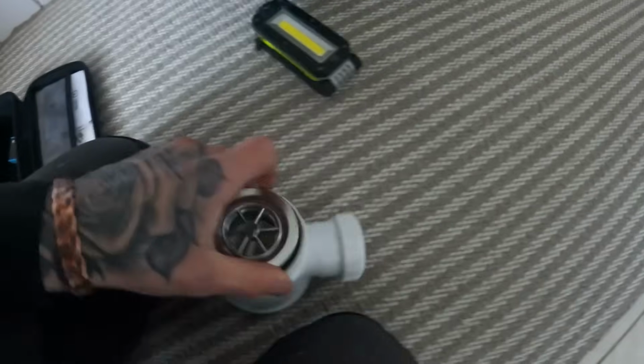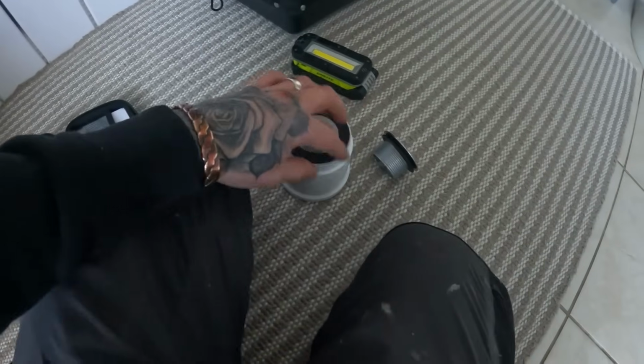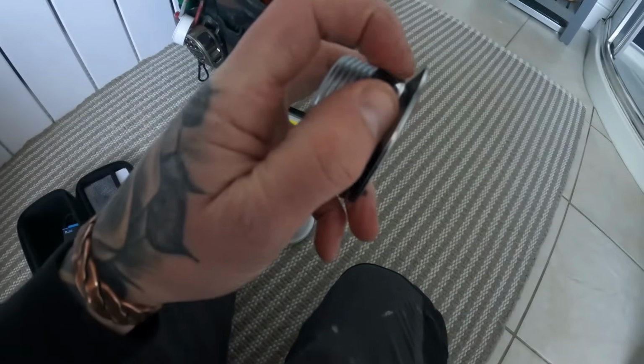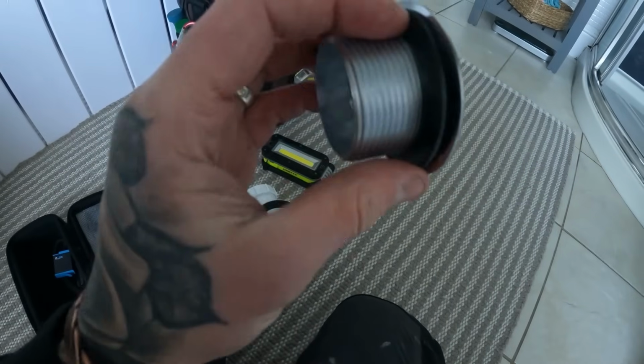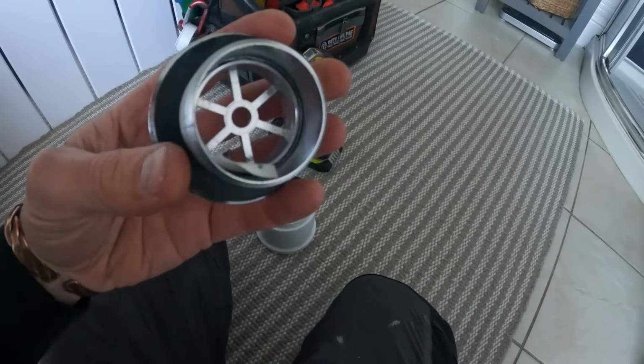So what I think it is, one of these star traps, the McAlpine ones. Obviously when you tighten this in, oh yeah, how long's the thread? When you tighten that in, it pulls that seal up underneath and creates a seal. But because this lip here has disintegrated and gone, there is nothing pulling that up, so it is going to pee out.